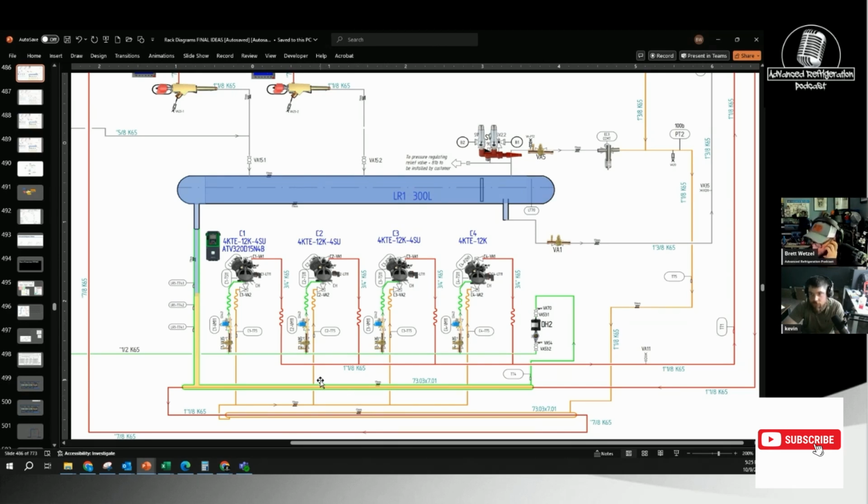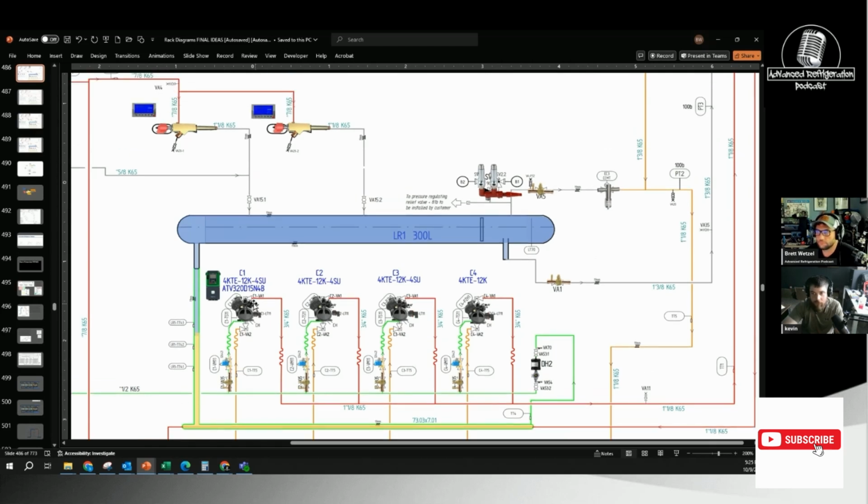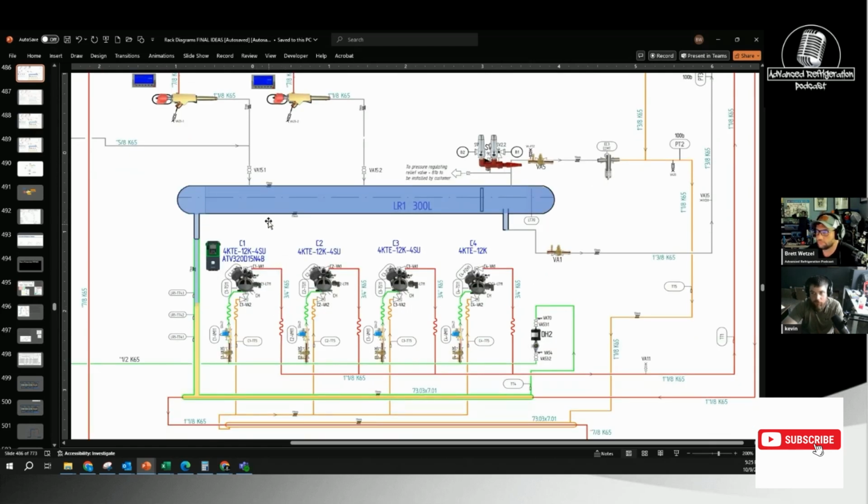That sounds fun. No, so that's been a thing. Other than that, it hasn't been too bad with the way it was designed. It could have always been worse, but I'm skeptical of what's going to happen when it's in a low temp, low load situation, because if you don't have anything to heat the oil, how are you going to get all the refrigerant out of it? You can't tell me there's not going to be any refrigerant liquid in there at all. If you lose oil, say if this thing starts pumping oil, you could pump some refrigerant through those crankcases pretty quick. If you get washed out because you had a washout situation or something happens and you lose oil, that's going to be a problem. I see.